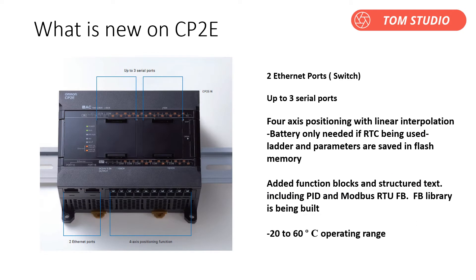Two Ethernet built-in ports — the two ports share the same IP address, so there is no need for an extra Ethernet switch to connect to external devices like an HMI or programming laptop. Up to three serial communications ports, and four-axis positioning with linear interpolation. Battery is only needed if RTC is being used; ladder and parameters are saved in flash memory. Added function blocks and structured text, including PID and Modbus RTU function blocks. The function block library is being built.